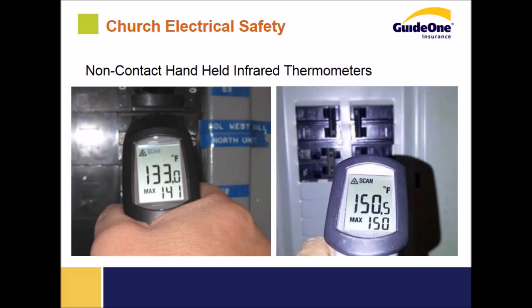We have issued infrared thermometers to our field staff, and they use them in a very simple way. These are not expensive. They're between $30 and $50, and they're certainly not as sophisticated as the infrared cameras, but they do a pretty good job of giving a quick reference temperature of electrical equipment. Our field staff just run them up the breaker panel, and when the temperature exceeds 120 degrees Fahrenheit, they take a picture of what you see in this slide, and they submit it in a recommendation that an electrician be brought in to find out what the problem is and make the corrections. It's an indication that there is a problem.